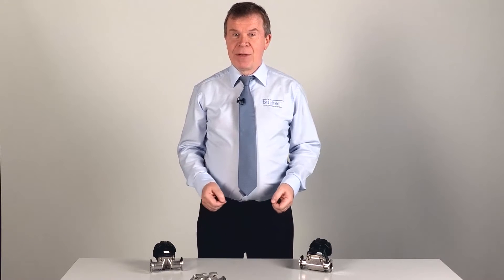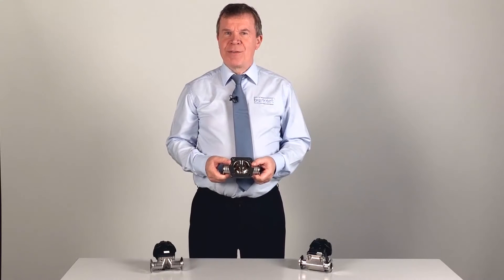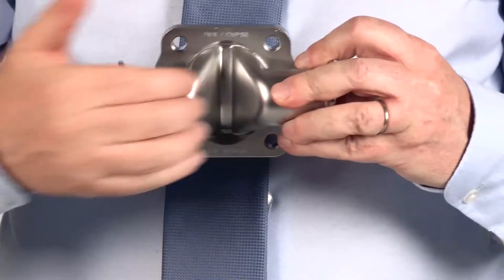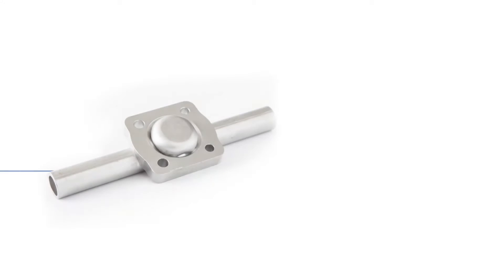We start with a length of 316L stainless steel tube and a matching supporting flange laser cut from the same material. The two components are then placed in the hydroforming machine, where they're subjected to a liquid pressure of over 3000 bar. Mandrels are forced inwards to produce a V-shaped weir on one side and a bulb on the other.